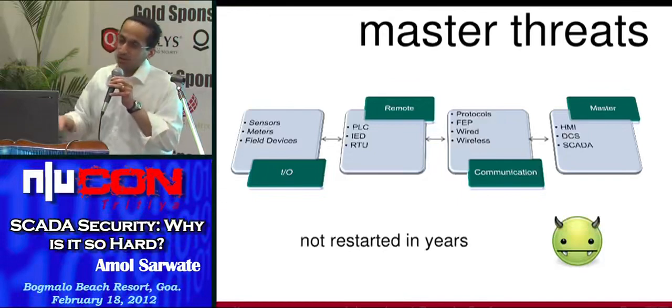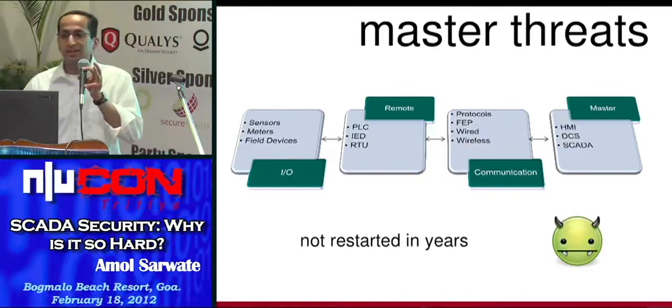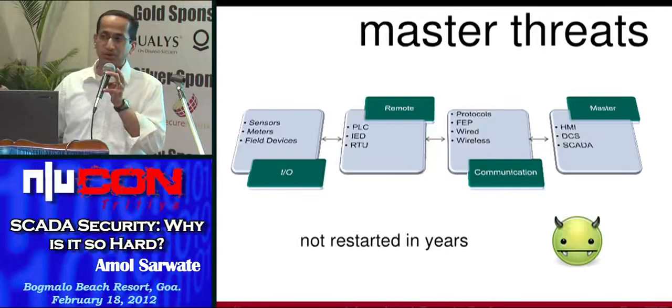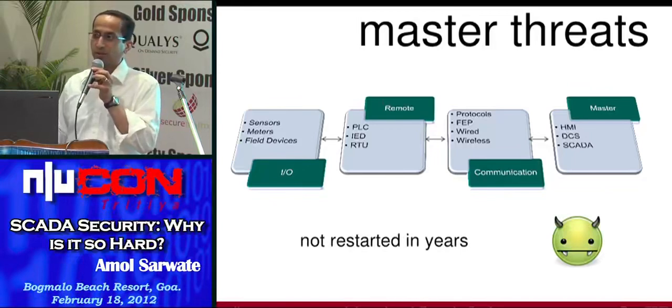Other things, well, we saw a lot of systems that have not been restarted in years. In SCADA, the lifespan of a system could be from 30 years to 40 years to even 80 years. When these systems are built, they are built to last even for like 100 years. We saw a lot of Windows 95 systems which were like 15 years old, and they have not been restarted even once. They have not been patched even once.